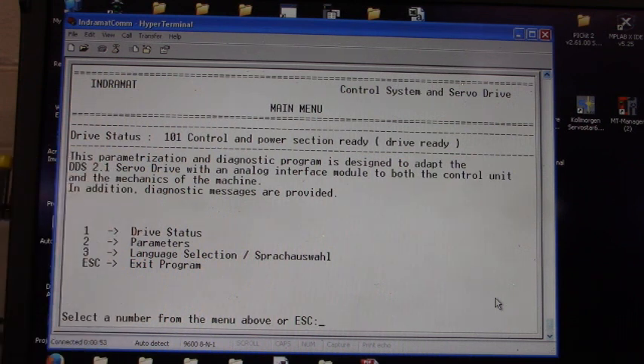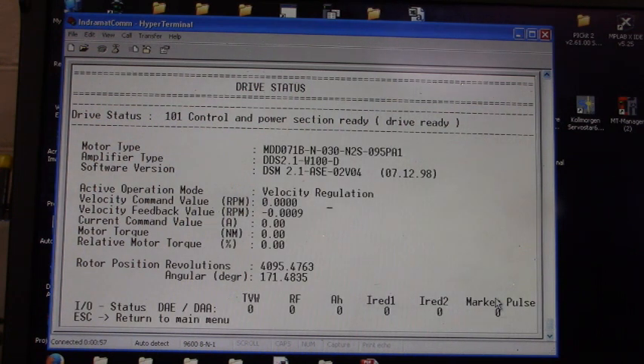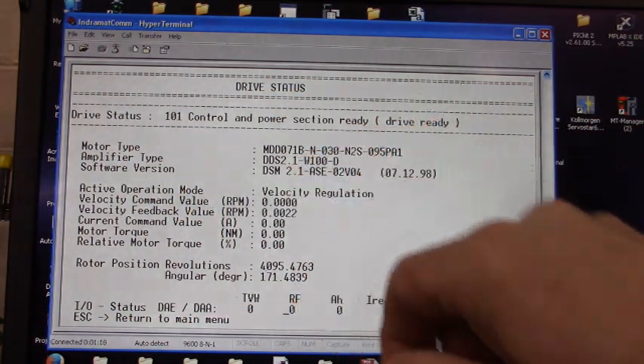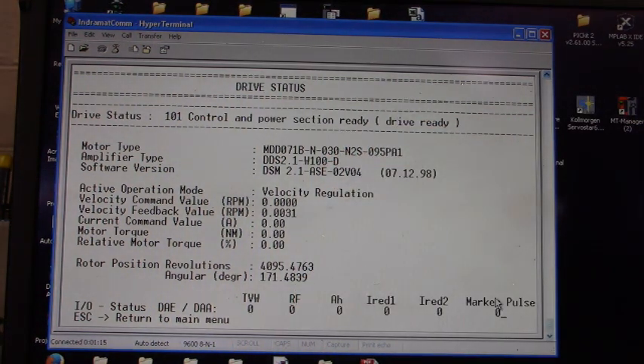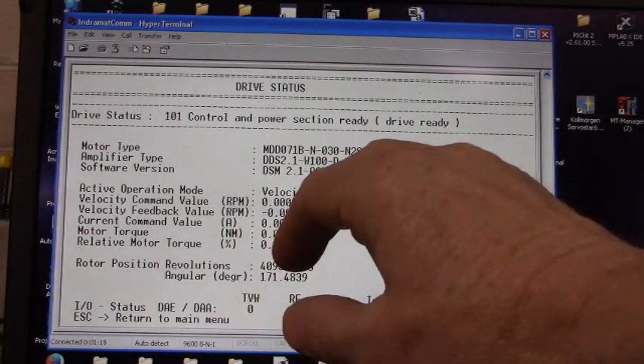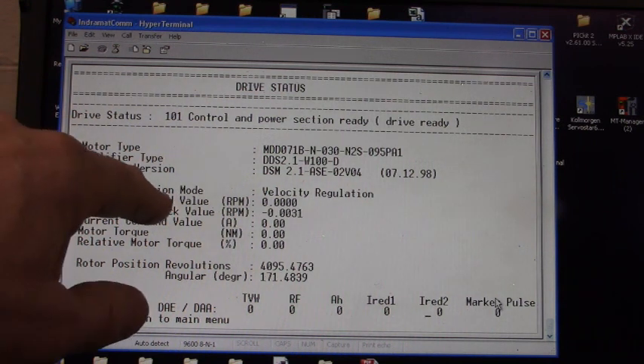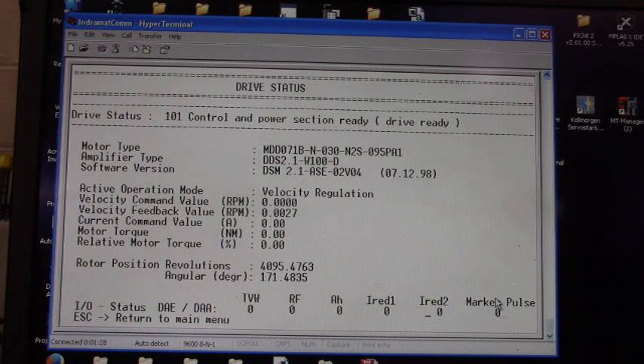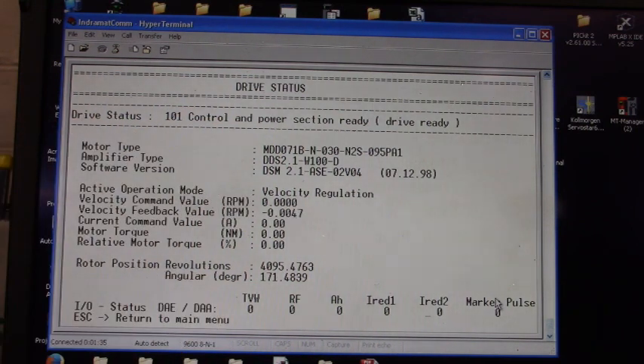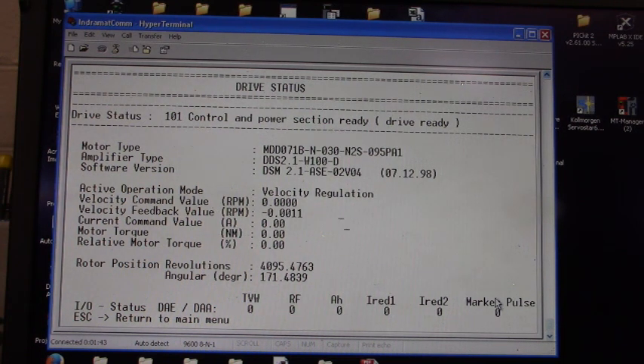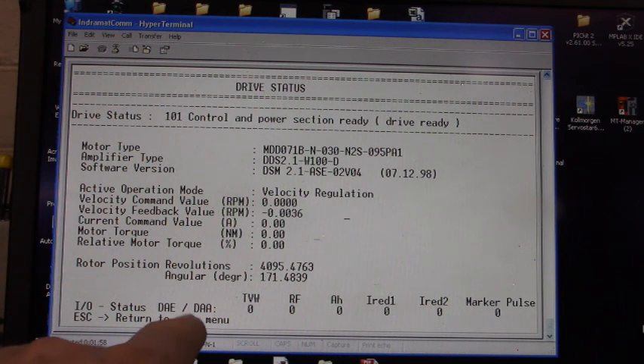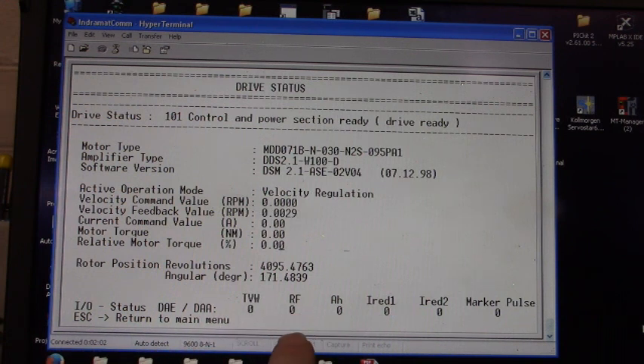We're going to press the number 1 key first and this is the drive status. It's pretty interesting. It tells us the motor type, the drive type, the software version, and these right here you can see them changing. The active operation mode is velocity regulation, and these are real-time values. If we were to run that motor we could look at the RPM, the current, torque in Newton meters. A lot of interesting data right there. Down here's some interesting items, there's the RF switch input and the AH switch input.